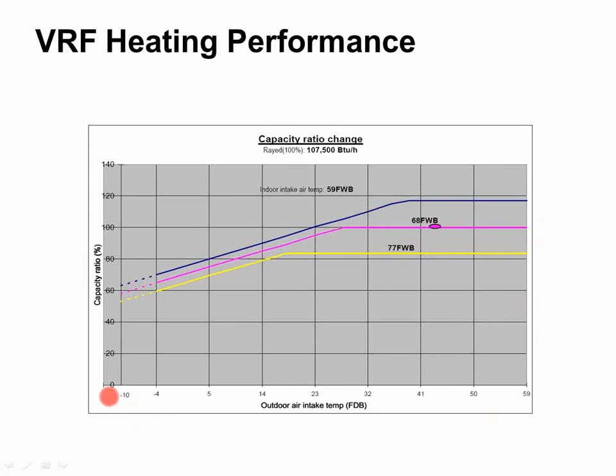So as you can see, the outdoor temperatures along the bottom go from -10 to 60 degrees. And as I'm lowering temperature outside, I'm maintaining my capacity. The way I'm doing that is I'm speeding things up. I'm ramping up the condenser fan to bring more air through the outdoor unit. And I'm ramping up the compressor. And I can also change the indoor fan speeds as needed.